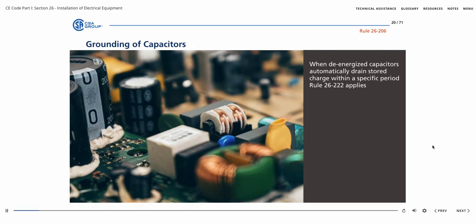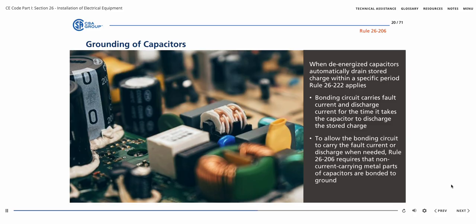When de-energized, capacitors automatically drain their stored charge within a specific period. See Rule 26-222. In this process, the bonding circuit not only carries fault current, but must carry the discharge current for the time it takes the capacitor to discharge the stored charge. To allow the bonding circuit to carry the fault current or discharge when required, Rule 26-206 requires that non-current carrying metal parts of capacitors are bonded to the ground.